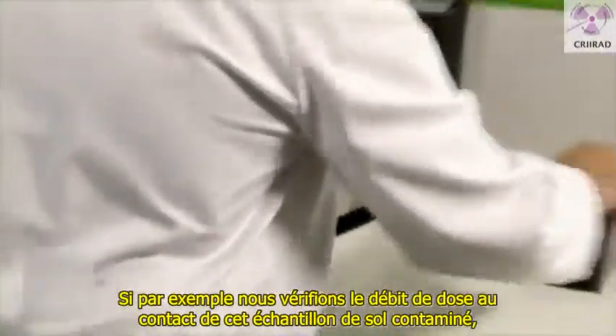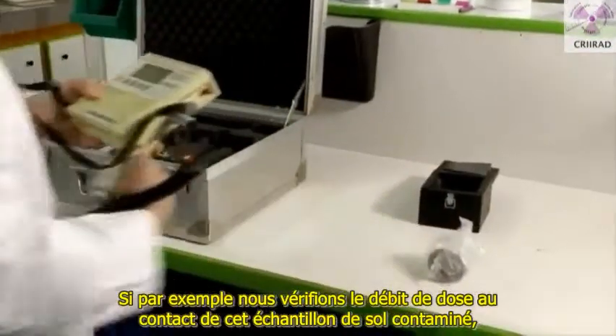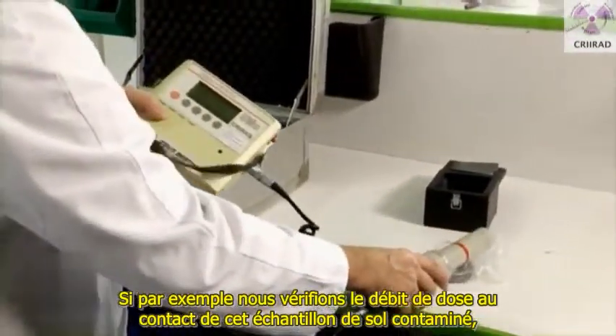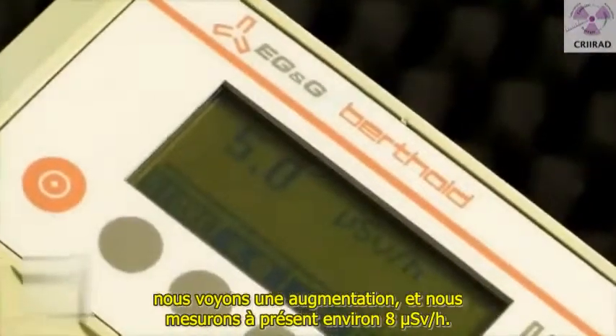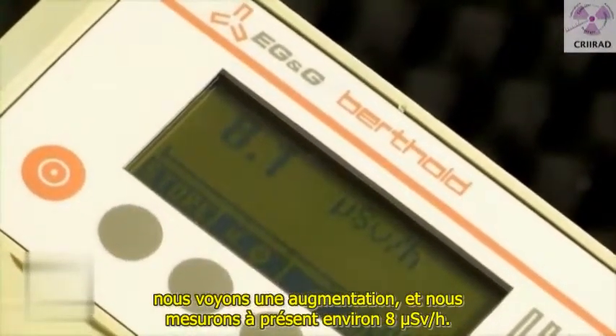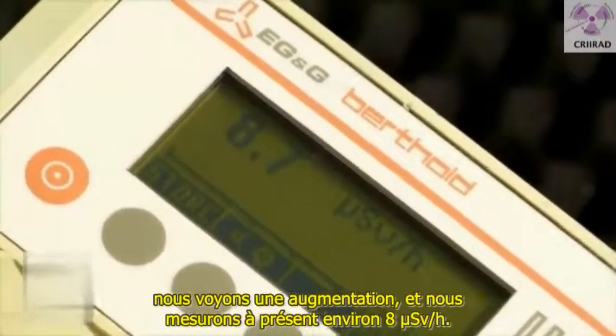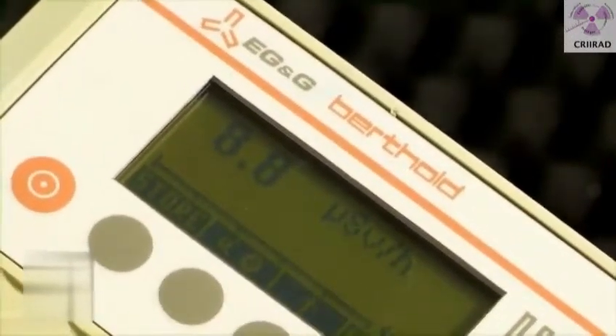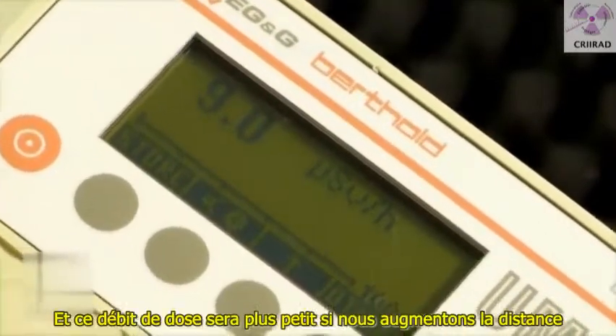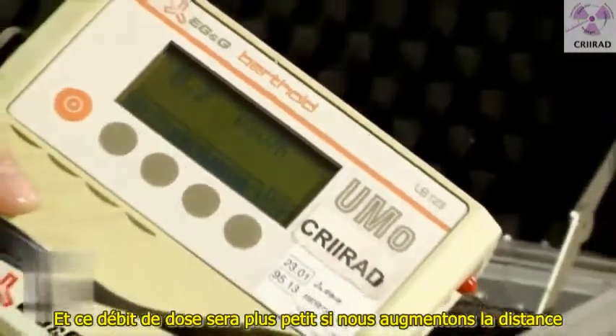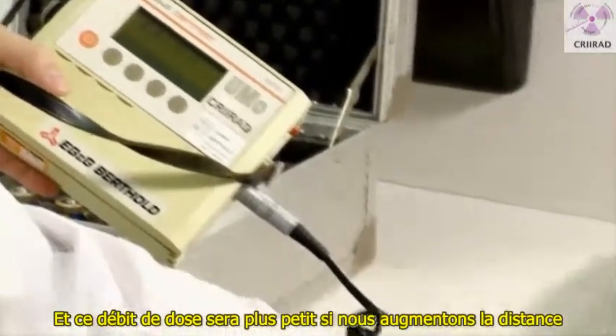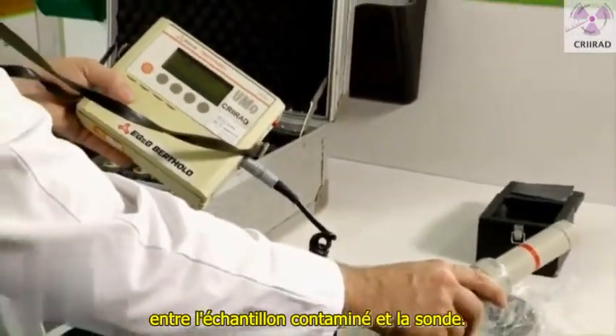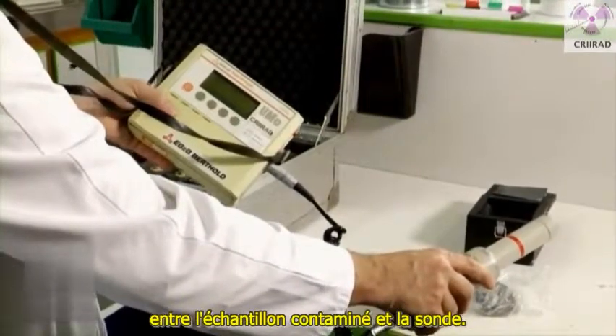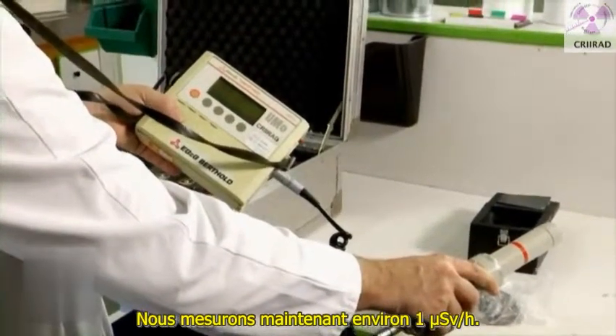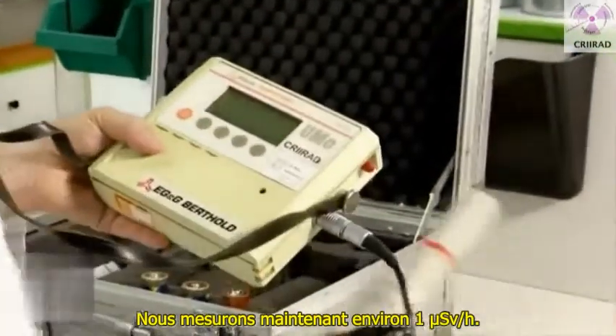So, for example, if we check the dose rate on contact of this sample of contaminated soil, we see an increase, and now we are measuring about 8 microsievert per hour. And this dose rate will be smaller if we increase the distance between the contaminated sample and the probe. We are measuring now about 1 microsievert per hour.